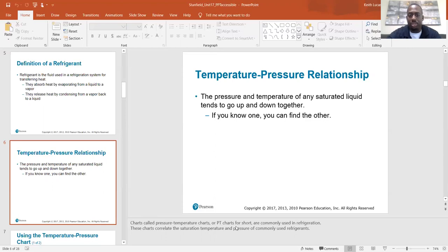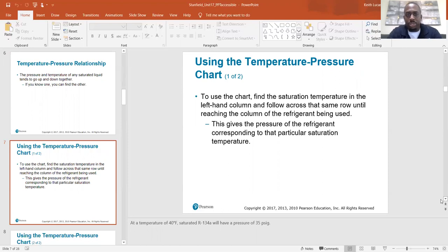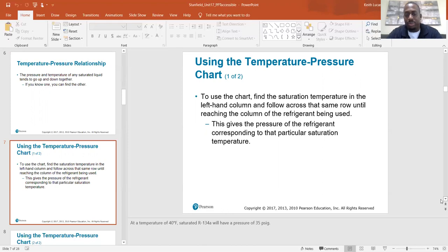PT charts are commonly used in refrigeration and correlate saturation temperature and pressure of commonly used refrigerants. To use the chart, find the saturation temperature in the left-hand column and follow across to the column of the refrigerant being used. This gives the pressure of the refrigerant corresponding to that particular saturation temperature. At a temperature of 40 degrees Fahrenheit, saturated R134a will have a pressure of 35 PSI.